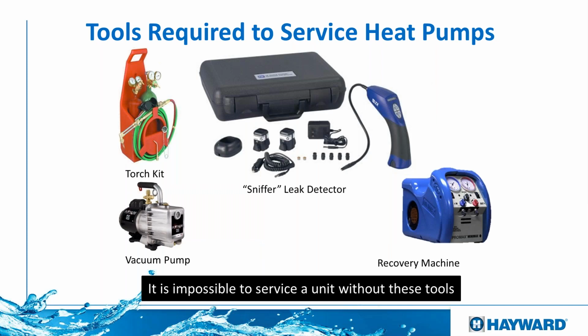And then once we have to open our refrigeration system, we need all of these tools, because there's no way to open a refrigeration system without the correct tools, including a torch kit in order to do any type of welding, and a sniffer or a leak detector. Like I mentioned before, all of our units are tested before they leave the factory. But remember that in the shipping process, especially international, all of that shaking and moving can actually get something loose. So it is important to have a leak detector in order to avoid any issues or to troubleshoot once we have an issue.